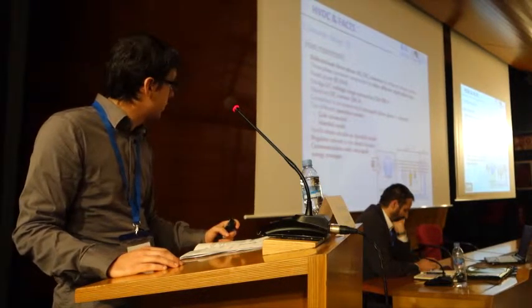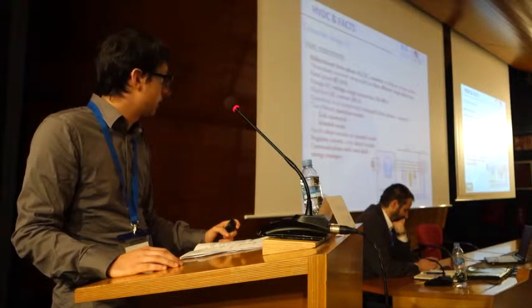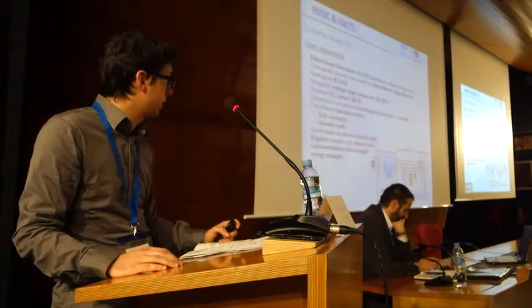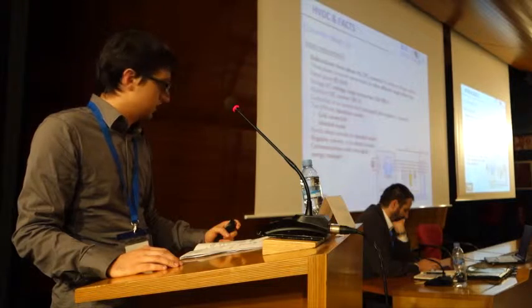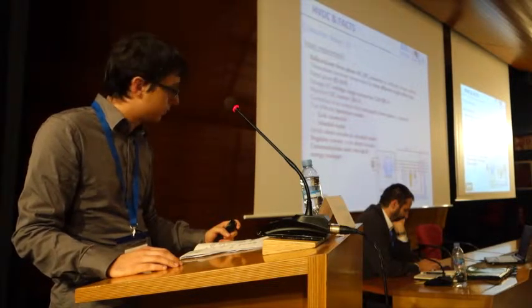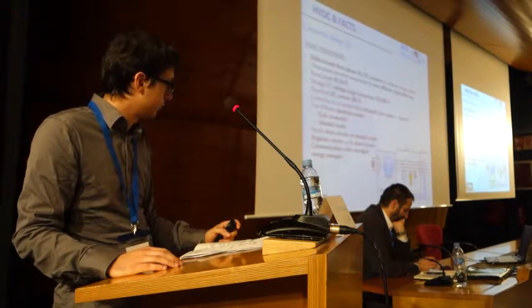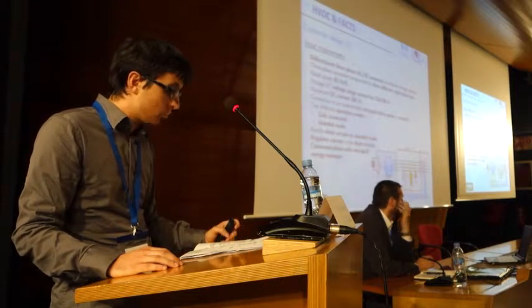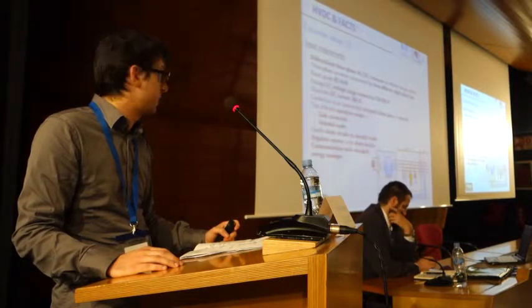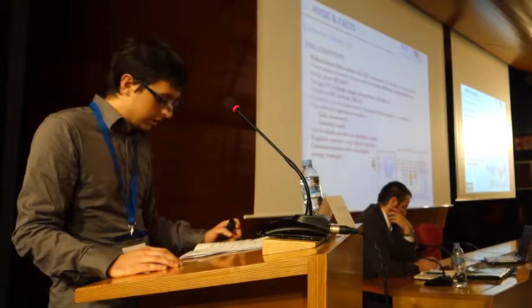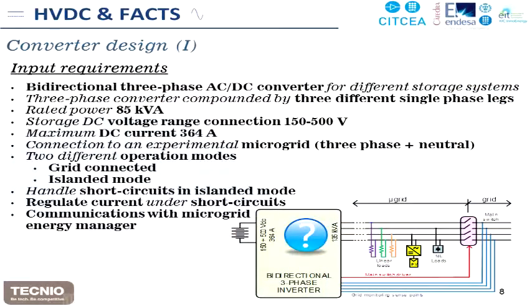The connection has been made to an experimental real microgrid located in Navarra, with an AC side of a three-phase four-wire microgrid. We have to operate the system in the two modes that I have mentioned, grid-connected mode and islanded mode. And one special issue is that we have to handle short circuits when we are operating in island mode.